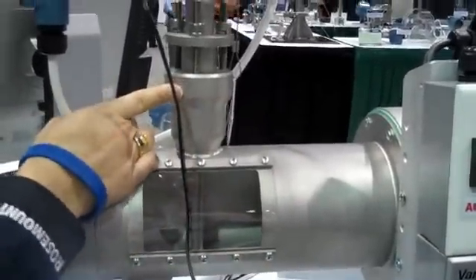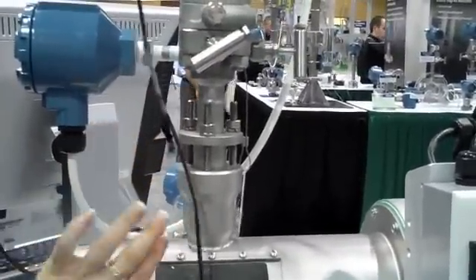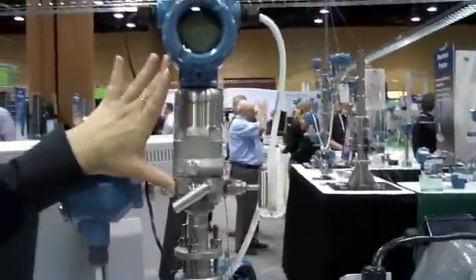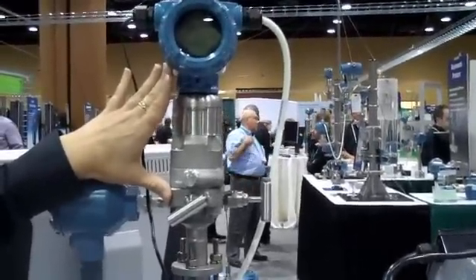This here is our Pak-Lok design, so it's going to have a simple one-hole drilled, welded design. It's a simple installation. As we go up, it's direct mounted to the transmitter, so you're eliminating impulse lines that are going to plug and freeze and other things.